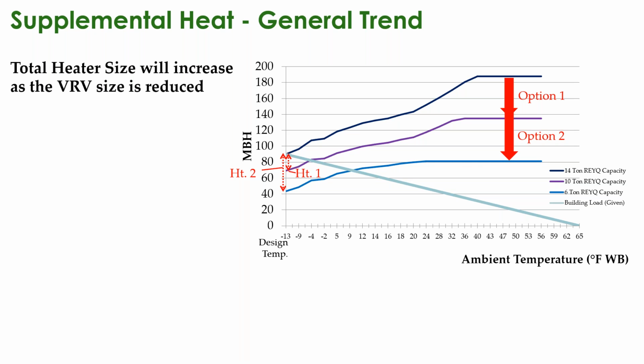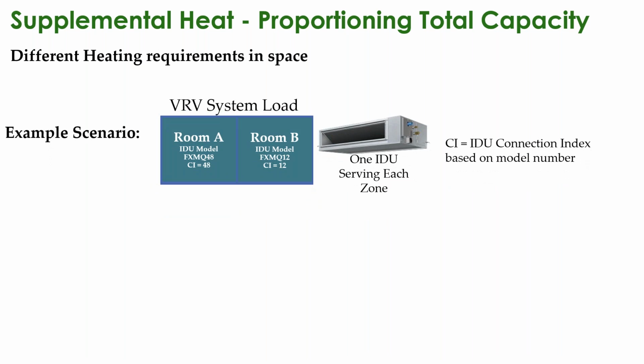For the amount of time that you're going to spend in that range, oftentimes the choice is the latter, that you're better off, it's better for the equipment to more right size that equipment and add that trim heat, increase the size of the trim heat, especially if you're going to put it on SCR style control, something that can modulate that. Again, we're assuming that you're going to have different heating requirements in each space. So in this example, we're looking at a total VRV system load with two fan coils connected to one outdoor unit.